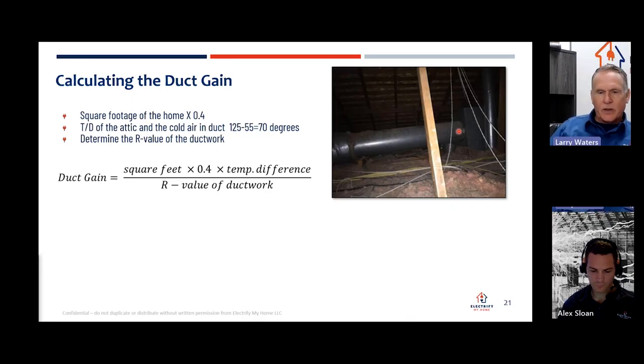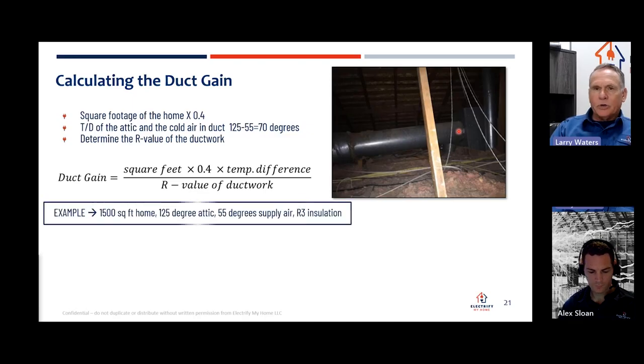So for quick perspective, if you have a 1,000 square foot house, you're going to have about 400 square feet of internal duct surface area. Okay, so we always use in all of our trainings a 1,500 square foot house as our trainer. So if we take this 1,500 square foot house, we just take a very conservative 125 degree attic. And any of you that have done HVAC work in Sacramento know that a 125 degree attic is a cool day in the summer. Okay, and we want 55 degree supply air coming through because we want our house to be 75. We've got about a 20 degree split.